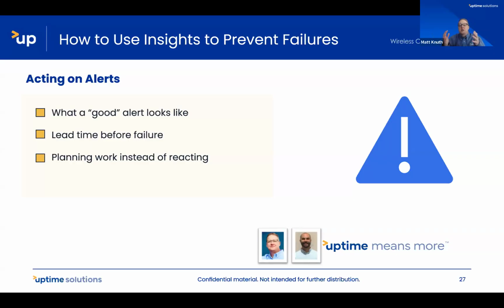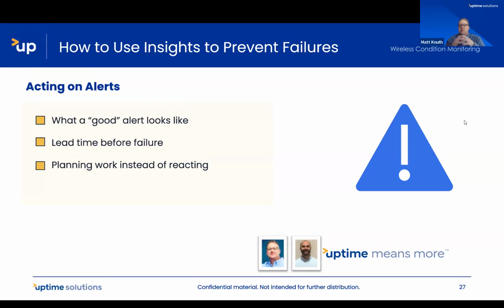Setting alarms—I'm going to spend a little time here, this is important. Setting alerts on variable speed or process heavy equipment is difficult, because you're trying to hit a moving target. In a variable system, the data changes constantly just because the machine is doing its job.